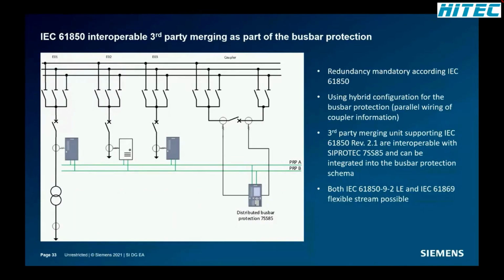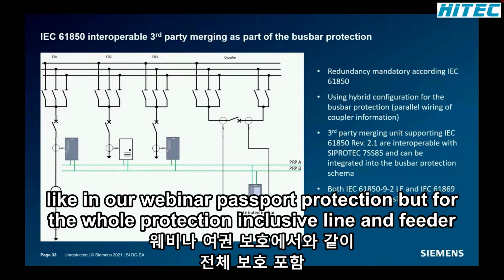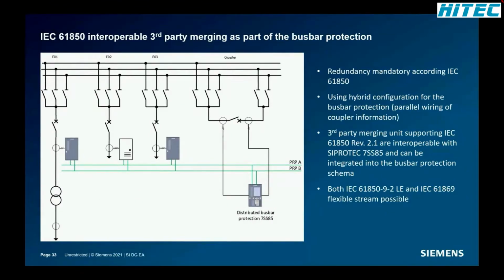Here, PRP, here's the lane PRP-A and lane PRP-B. The reason is that in a digital substation, the communication is not only the precondition for one protection type, like in our webinar, the busbar protection, but for the whole protection, including line and feeder protection. Therefore, a loss of the communication would lead to the loss of the complete protection. And we will see this in the next slides.